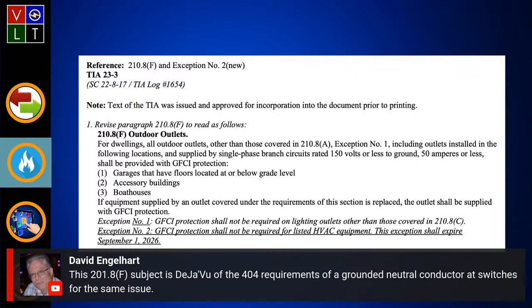What the problem with this is, David, is if you look at a switch there, where that switch goes, there's an outlet there, which is the box. So that is 2 different issues. What the issue is here with 210.8F is them calling the AC unit, in my opinion, an outdoor outlet. I do not agree with that. I agree with the sentiment about the grounded neutral conductor, but if that's what they're worrying about, I feel — this is my opinion once again — I feel if you want GFCI protection for that AC unit, it should be in 210.8D for specific appliances like they do everything else. They shouldn't be calling this an outlet.